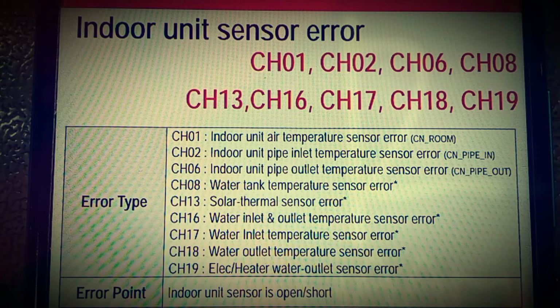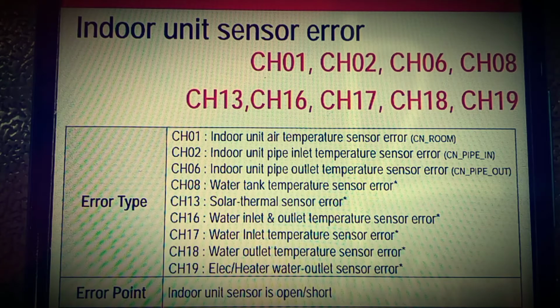As you can see in the list of error types, CH01 stands for indoor unit air temperature sensor. Whenever your indoor unit air temperature sensor is faulty, CH01 will appear on your display. CH02 is indoor unit pipe inlet temperature sensor error, 06 is indoor unit pipe outlet temperature sensor error, and 08 is water tank temperature sensor error.